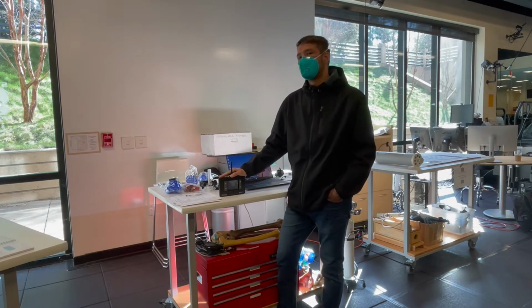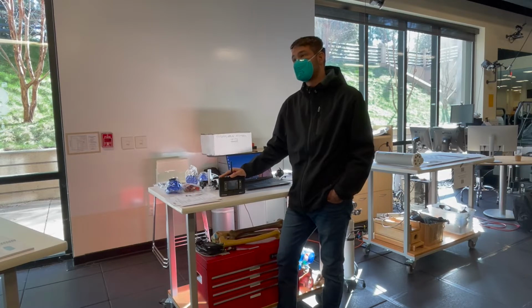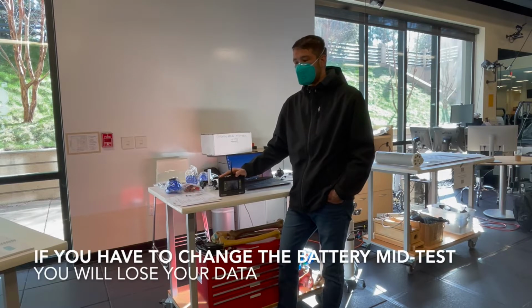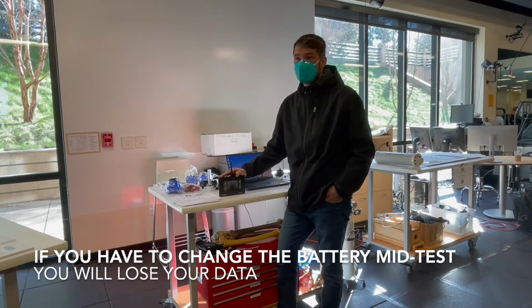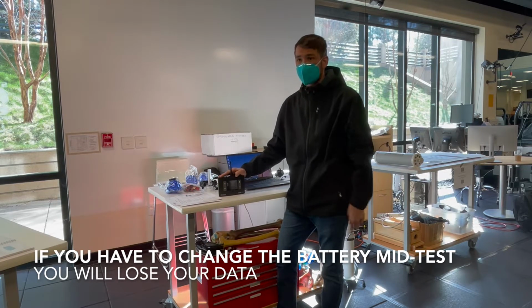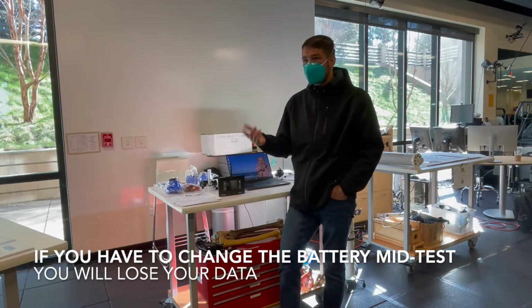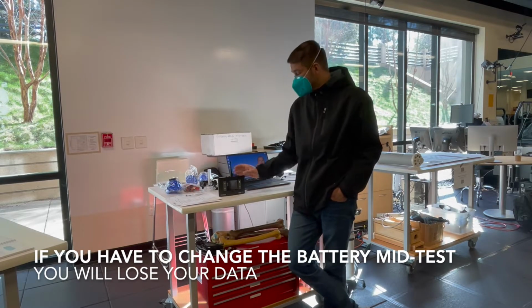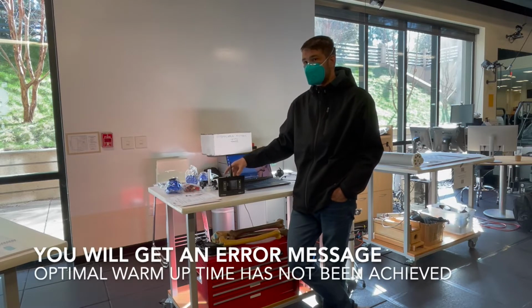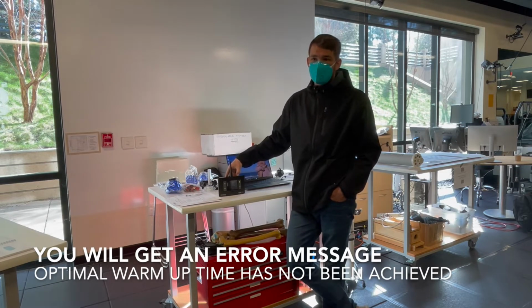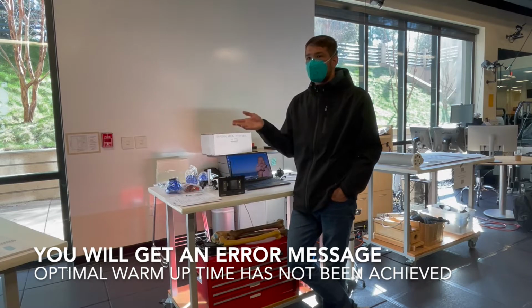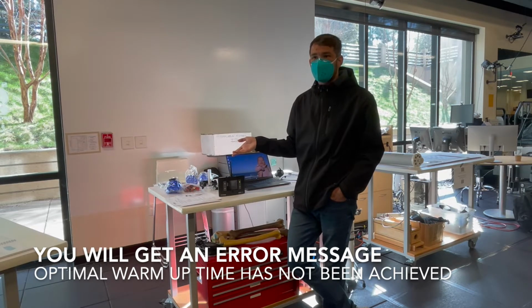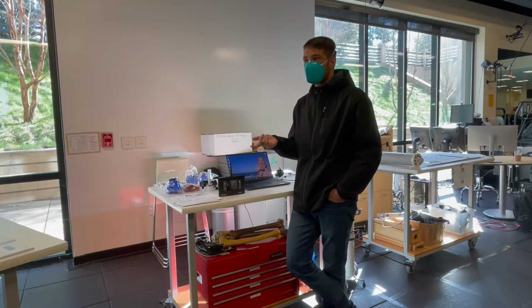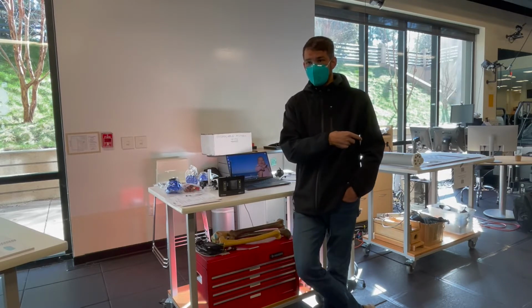You want to make sure that both of your batteries are sufficiently charged before testing. You don't want to run into the issue where you have to change the battery mid-test. You're gonna lose the data essentially after it dies. You'll have everything saved up to the point in which it dies. You could get the new battery in and continue testing, but it's going to give you an error message basically saying that optimal warm-up time hasn't been achieved. You can kind of disregard that in a sense, because it has been warmed up, it just got shut off, and there's nothing in the code that tells it you were just on.